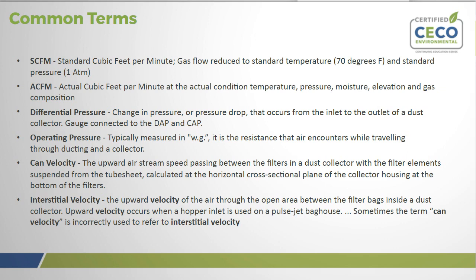CAN velocity and interstitial velocity are terms that are sometimes used interchangeably, though somewhat incorrectly. CAN velocity is the upward airstream speed passing between the filters in a dust collector with filter elements suspended from the tube sheet, calculated at the horizontal cross-sectional plane at the bottom of the filters. Interstitial velocity is the upward velocity of the air through the open area between the filter bags inside a dust collector, and occurs when the hopper inlet is used on a pulse jet bag house.